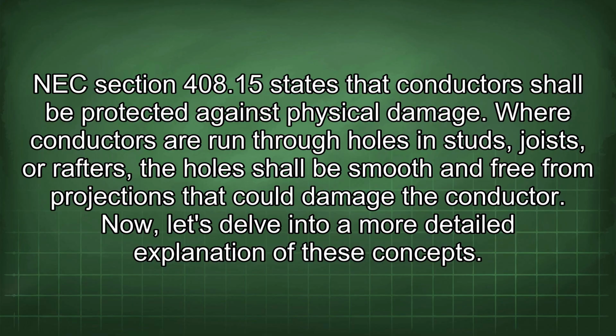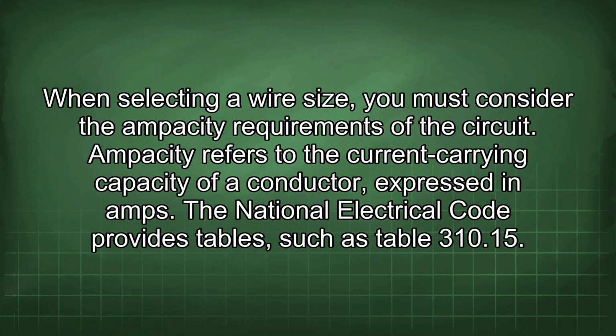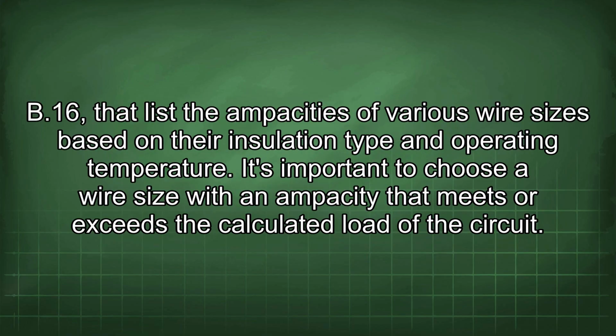Now let's delve into a more detailed explanation of these concepts. When selecting a wire size, you must consider the ampacity requirements of the circuit. Ampacity refers to the current carrying capacity of a conductor expressed in amps. The National Electrical Code provides tables, such as Table 310.15(B)(16), that list the ampacities of various wire sizes based on their insulation type and operating temperature. It's important to choose a wire size with an ampacity that meets or exceeds the calculated load of the circuit.